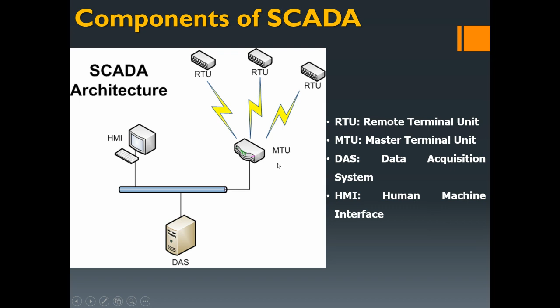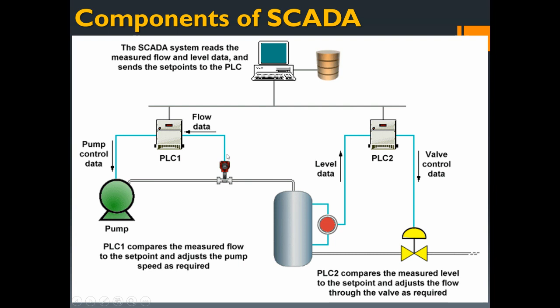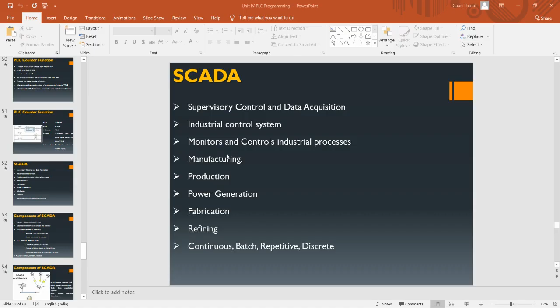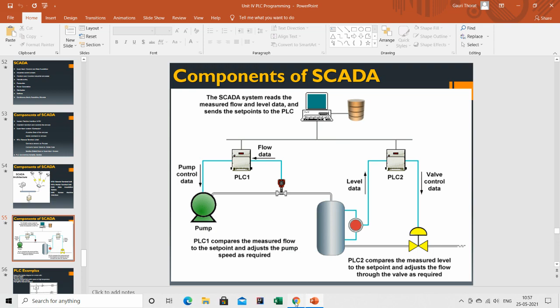We have this plant with a tank, and some liquid level is to be maintained in the tank. Also, the flow has to be regulated. The liquid level is maintained with the help of level sensors, and the flow is adjusted with the help of this pump control data. Here we have installed two PLCs. PLC1 compares the measured flow to the set point and adjusts the pump speed as required. PLC2 compares the measured level to the set point and adjusts the flow through the valve as required. The valve control data and the flow data go through the PLCs. They are sent to the SCADA system, where they are read and monitored with the help of this screen, which we call the human machine interface. So the SCADA system reads the measured flow and level data, and it sends the set points to the PLCs. This is how supervisory control and data acquisition works.